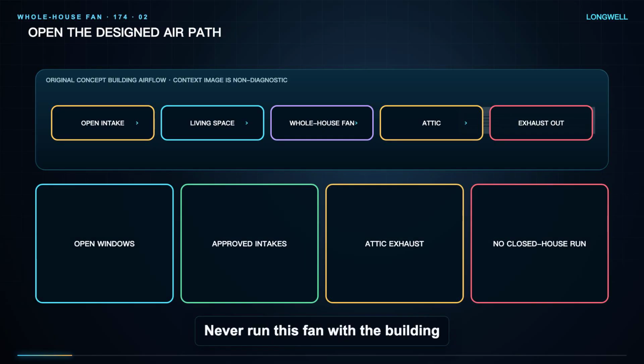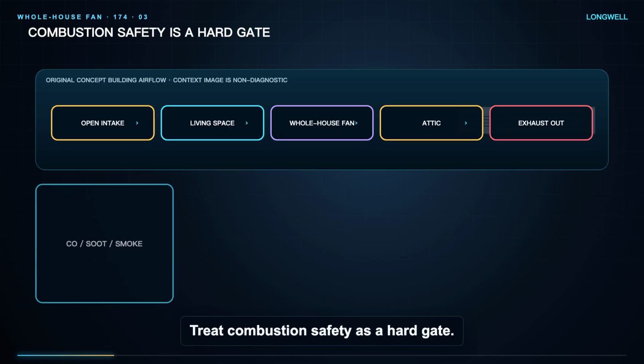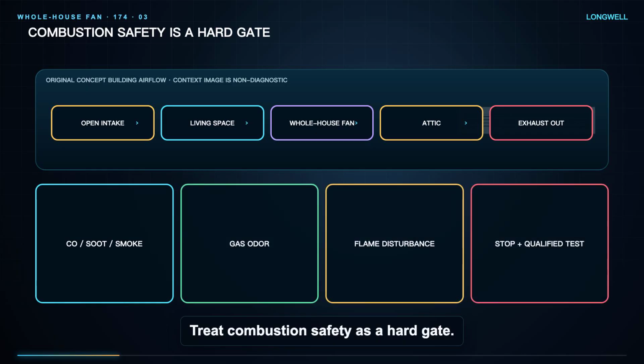Never run this fan with the building closed. Open the required windows or other approved intakes, and confirm that the attic has the designed exhaust path. A blocked intake or attic outlet can create excessive pressure, noise, shutter problems, and poor airflow even when the motor is healthy. Treat combustion safety as a hard gate.